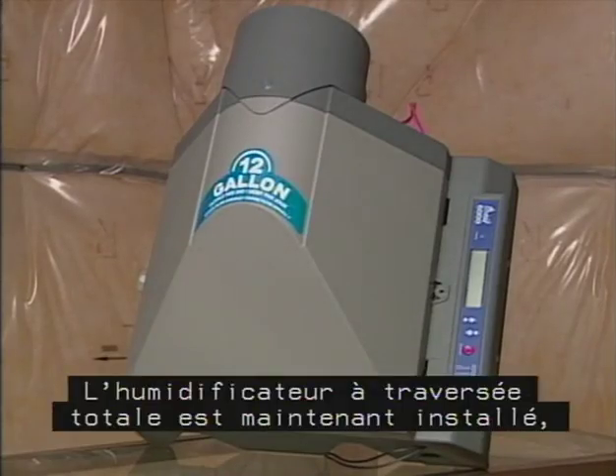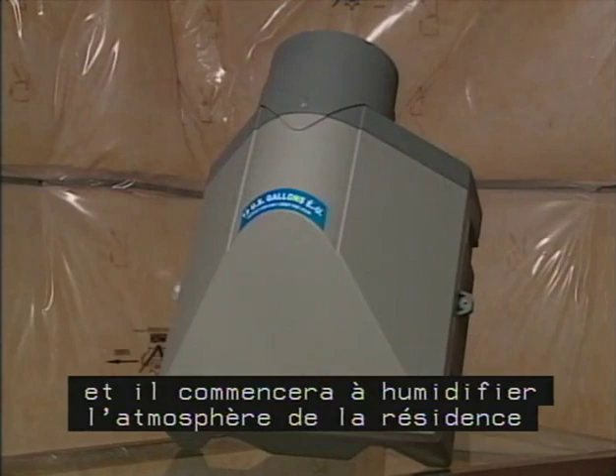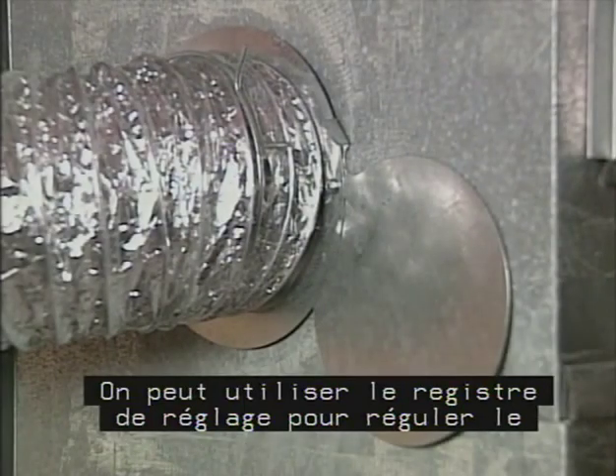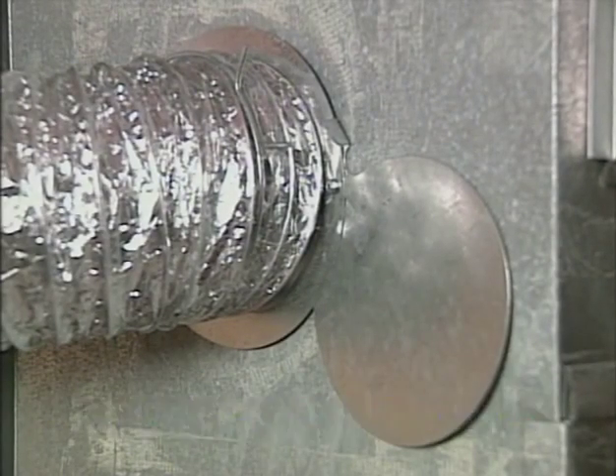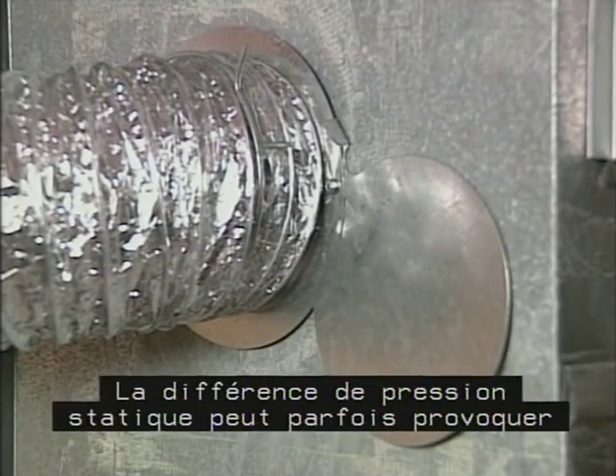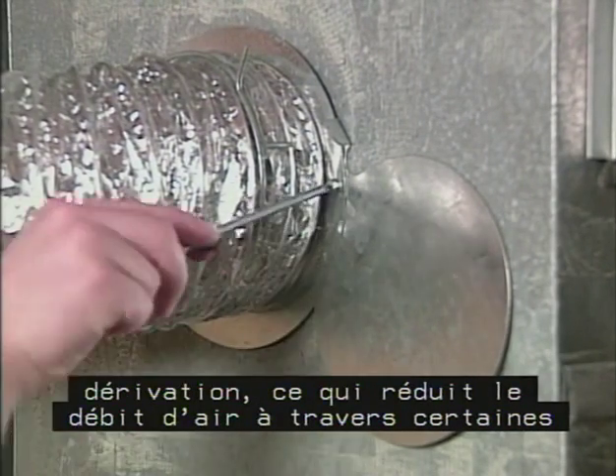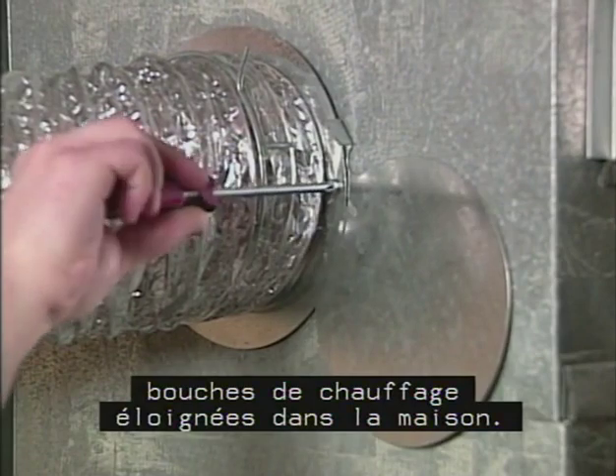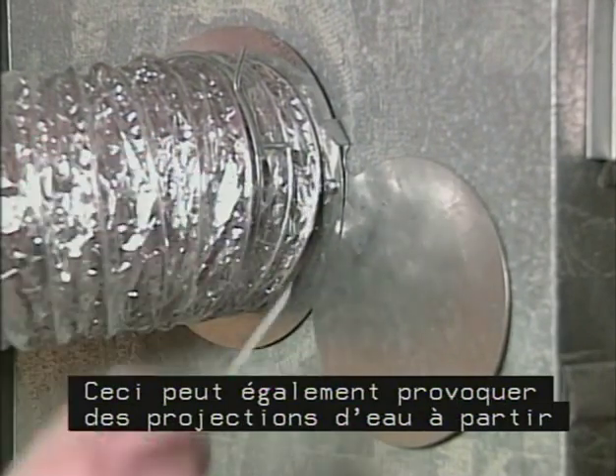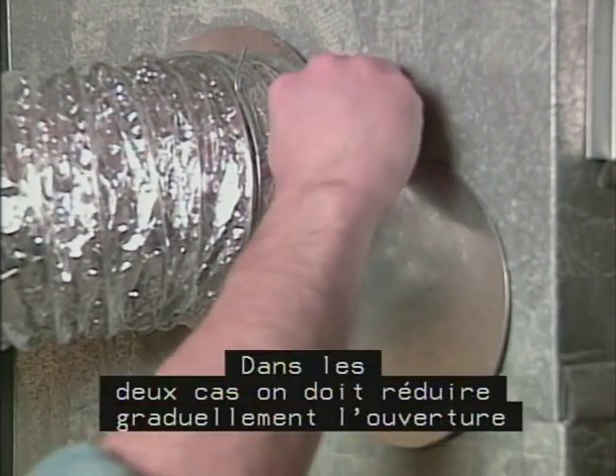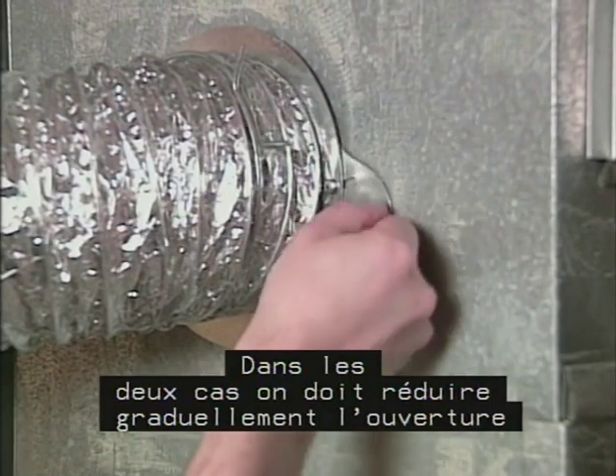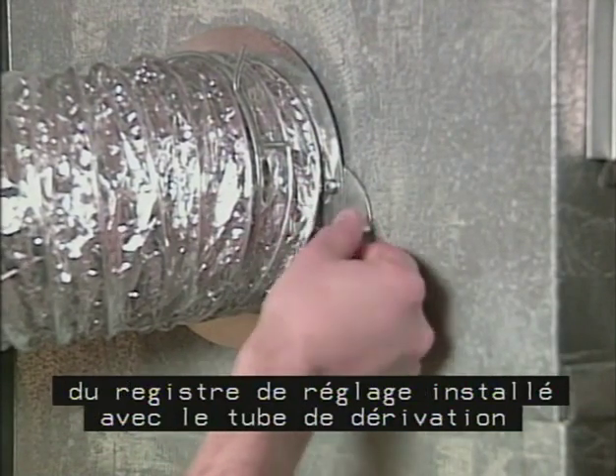Your flow-through humidifier is now installed and will begin humidifying your home with the next furnace cycle. The bypass damper can be used to regulate bypass airflow. Sometimes there can be a static pressure differential that may cause an excess of air to flow through the bypass tube, causing less airflow through the distant heat outlets in the house. It may also blow water off the evaporator pad. In either case, the air damper installed with the bypass collar should be gradually closed until the condition is corrected.